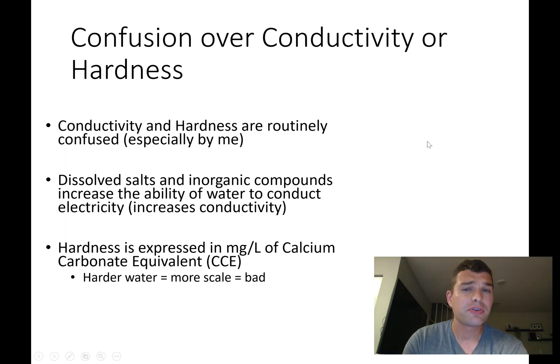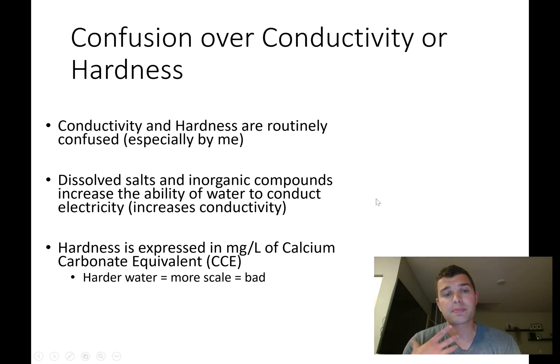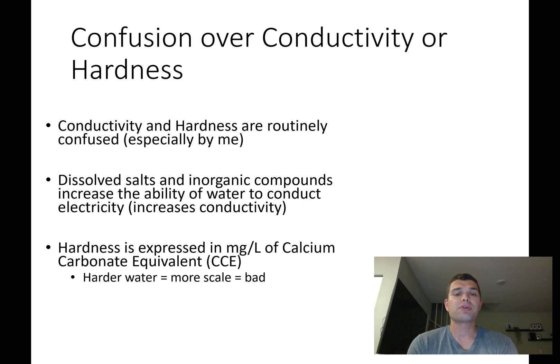There's a lot of confusion over conductivity versus hardness. Dissolved salts and inorganic compounds increase the ability of water to conduct electricity, which increases conductivity. Hardness is expressed in milligrams per liter of calcium carbonate equivalent, and it accounts for magnesium or calcium only.